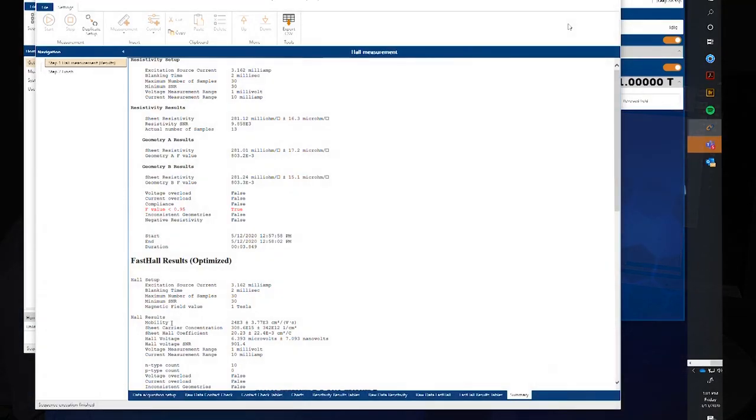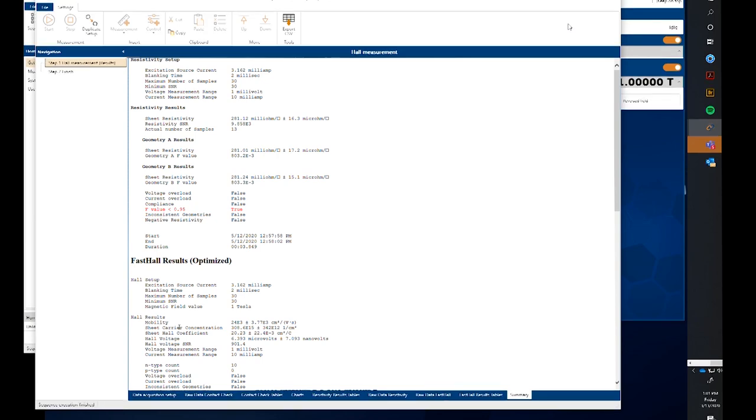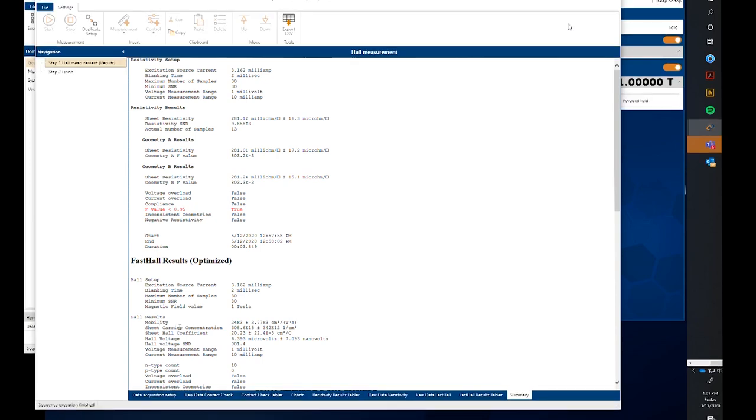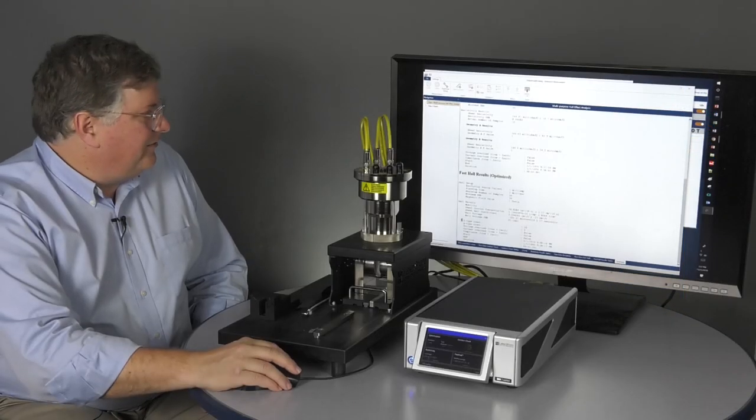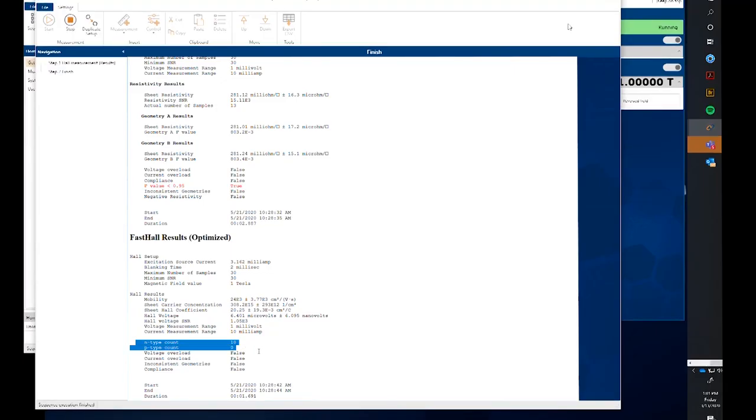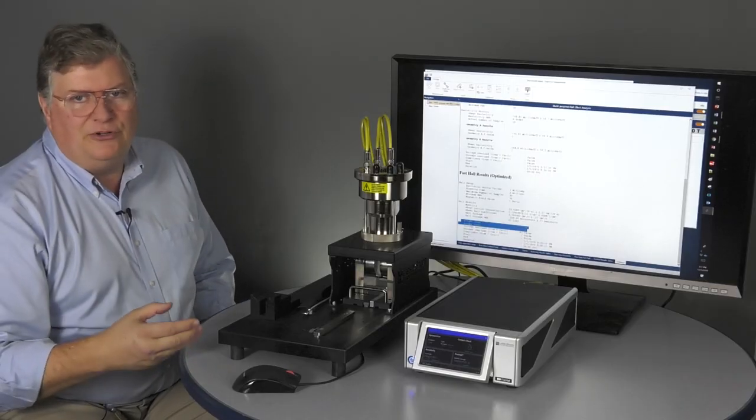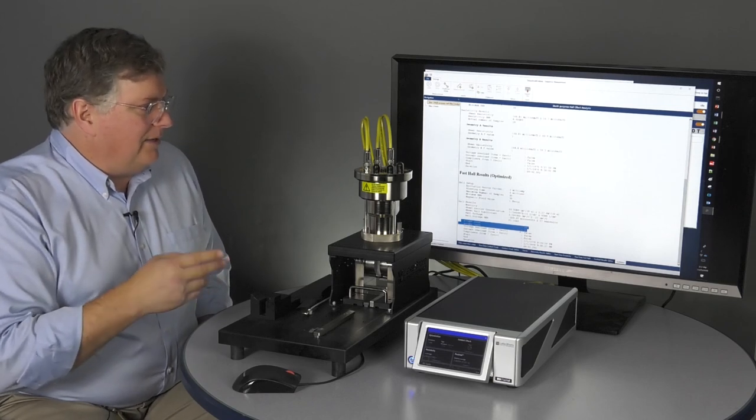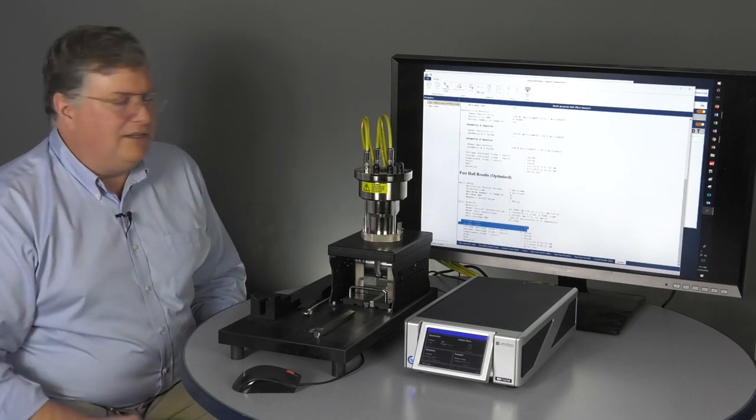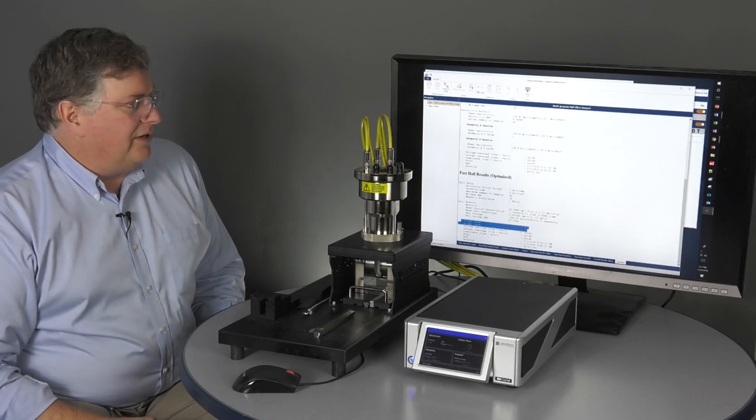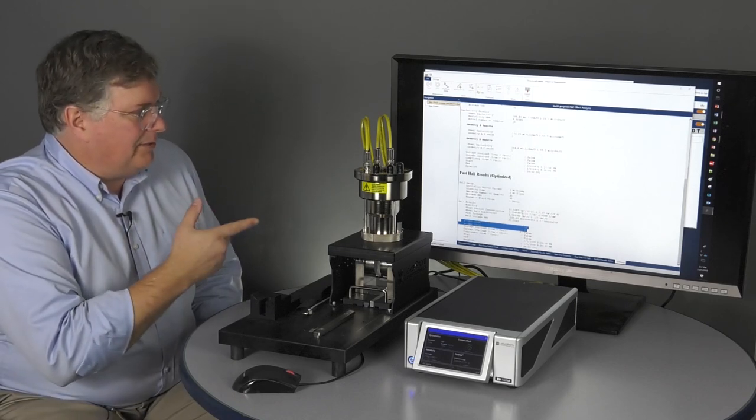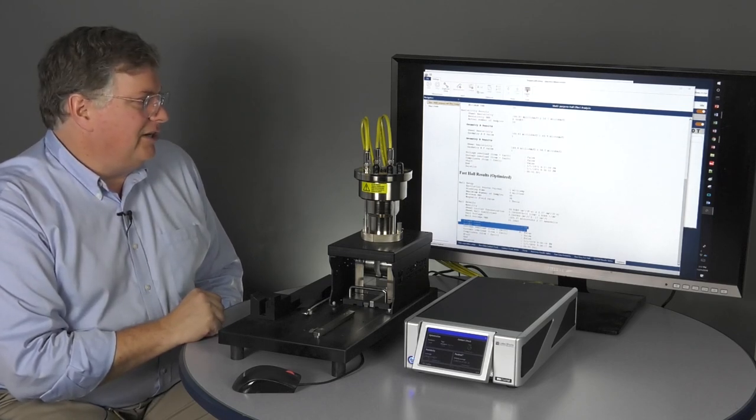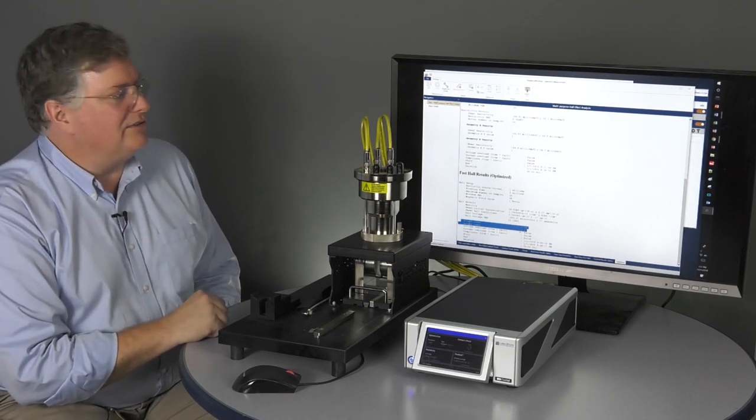For fast hall, so this is an indium arsenide sample. 24 times 10 to the 3 centimeters squared per volt seconds is a fine value. Also shown, and not so important for this sample, is for each of the different calculations, it shows how many p-type determinations and how many n-type were shown. So, if you were measuring a difficult sample and your noise band became close to the hall voltage, what you can get some, any one sample may have some chance of coming in either n-type or p-type. And so, what you can see is for each independent evaluation allows you to get a very good determination of the material type, even for a difficult sample.